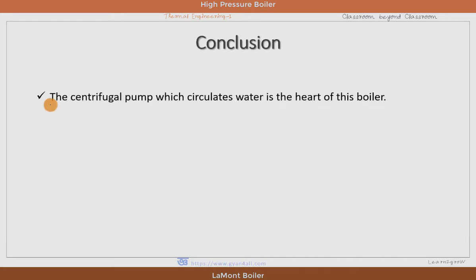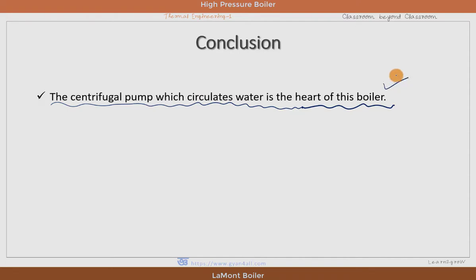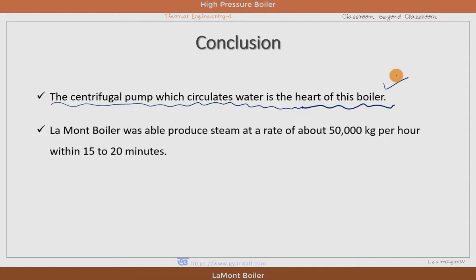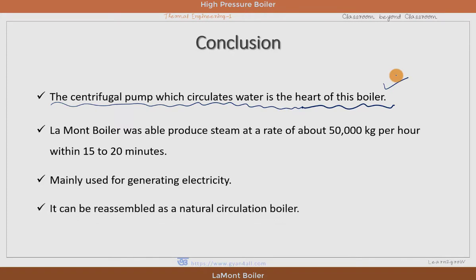As a conclusion, the centrifugal pump which circulates water is the heart of the boiler, because the pressure developed by the boiler is actually given by the centrifugal pump which supplies the water inside the boiler. The Lamont boiler is able to produce steam at a rate of about 50,000 kg per hour within 15 to 20 minutes, which means easy starting. This boiler is mainly used for generation of electricity. It can be reassembled as a natural circulation boiler by removing the circulating pump with a little modification, although it is designed as a forced circulation boiler.